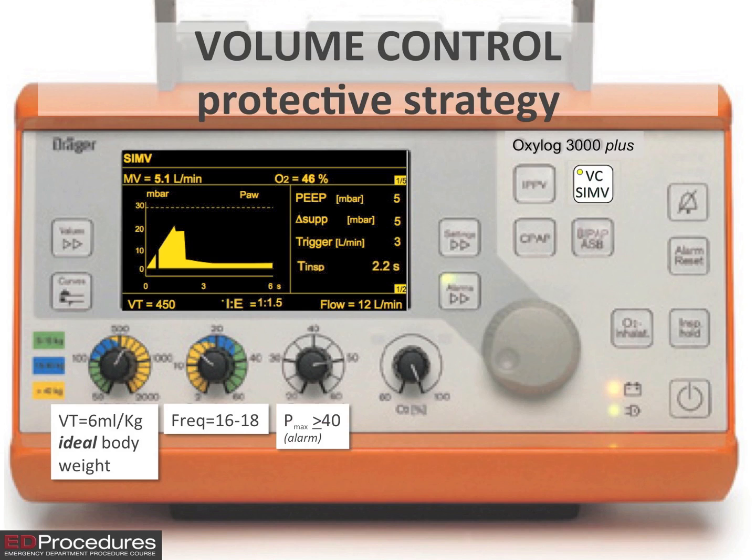Next is the Pmax knob. It doesn't set a pressure, it sets an alarm to go off if the pressure in the circuit exceeds the nominated value. The nurses refer to it as a PIPS, or peak inspiratory pressures. Unfortunately, it does not relate to anything useful to the patient.